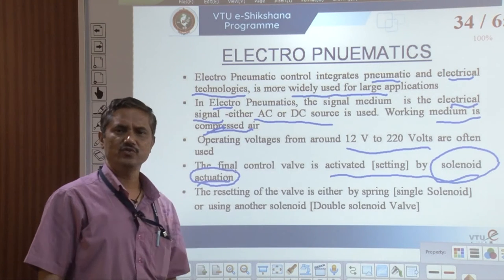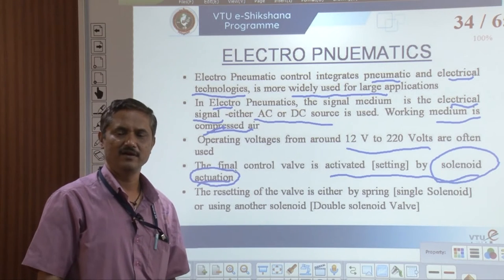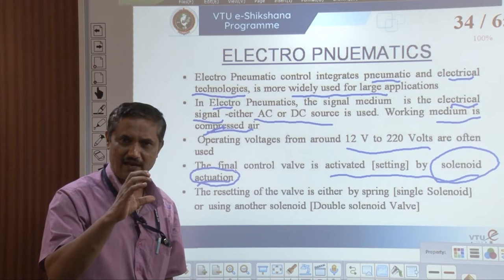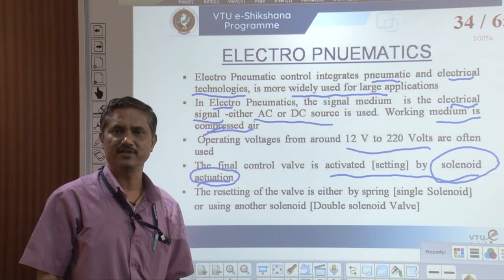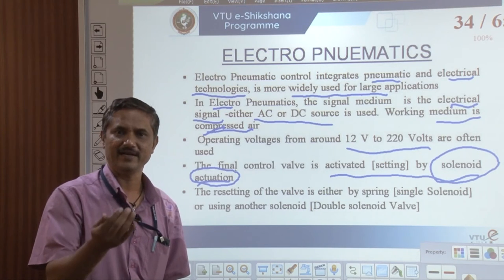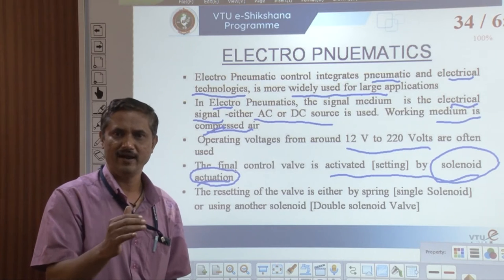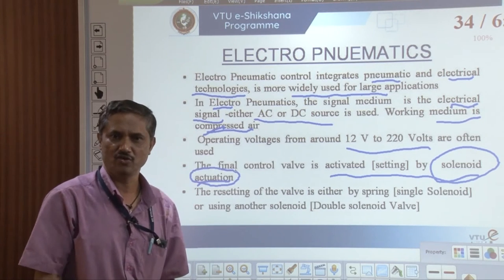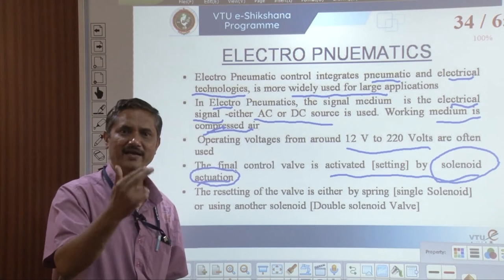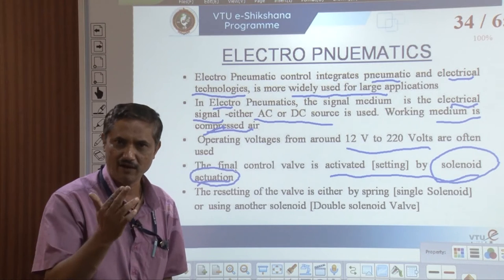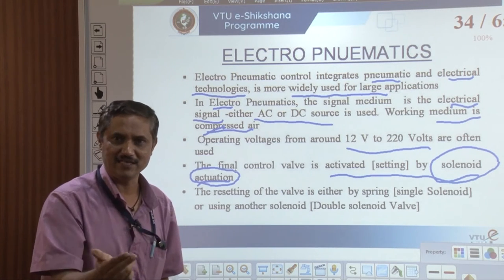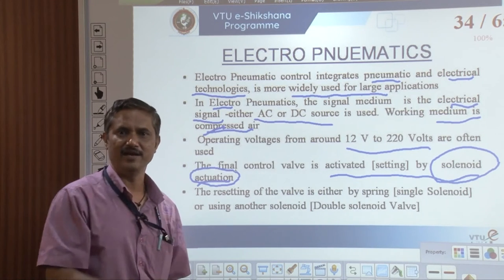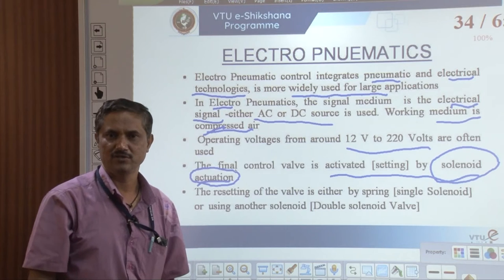You need to understand what solenoid actuation is, and before that, what a solenoid is. A solenoid controls a valve, that is, the opening and closing of the valve with the help of an electrical signal. When you give power, the power induces a force in the valve that pulls or pushes it, so that the valve operates due to the electromagnetic induction force created. So we are energizing and de-energizing the valve, creating a force to open and close it with the help of that electrical energy.